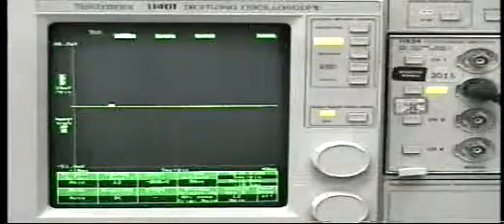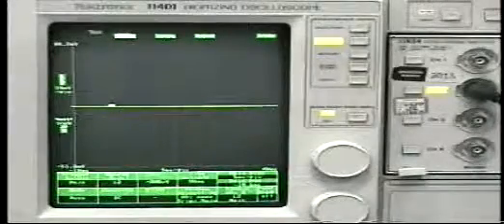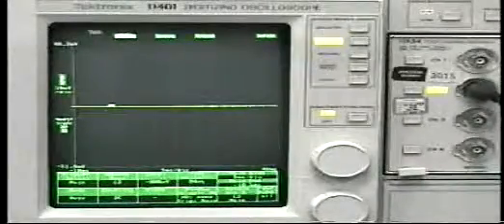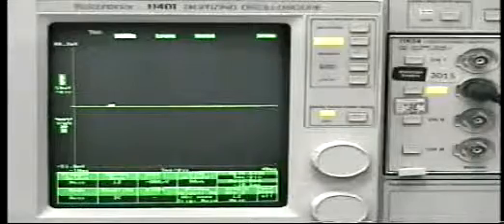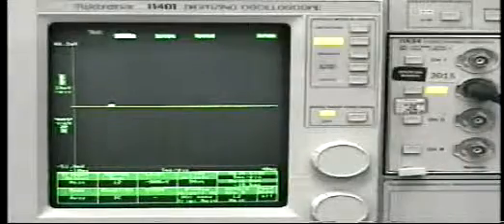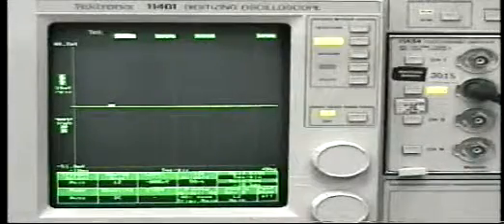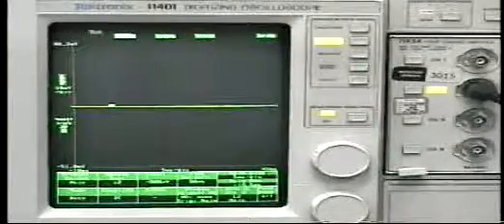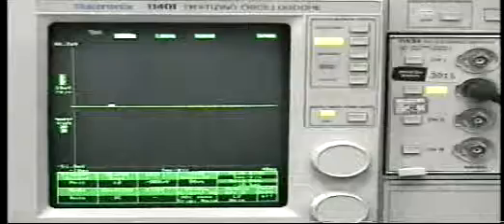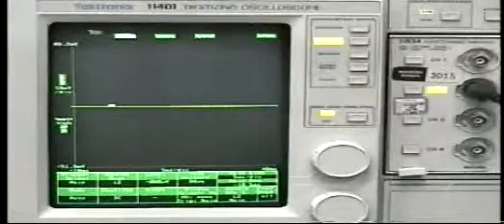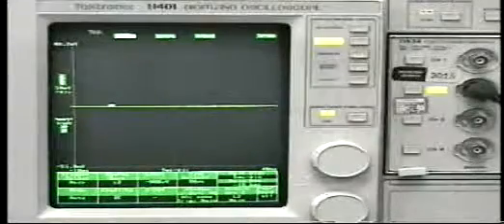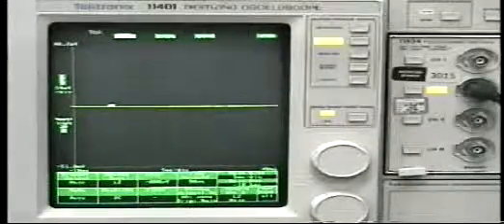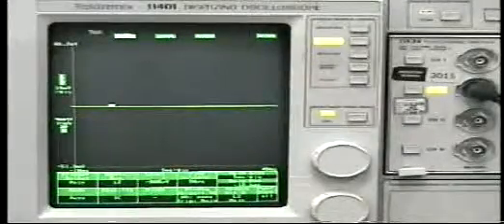This is an example of the heater bakeout function. The nominal load current for this load is 4 amps. We have set the overcurrent trip at 6 amps. If the load current exceeds this trip point, the output shuts off and trips a heater bakeout error.